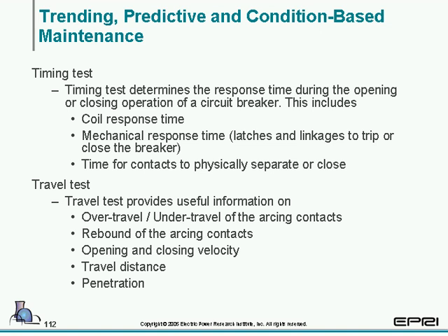The timing test is a fairly easy test to perform. The timing test can be done during a PM. A lot of times it is, but the travel test is a much more involved test. It requires much more setup, and it provides additional information for the extra work you have to do. It'll provide over travel and under travel of the arcing contacts, and this is in the form of an actual printout. It'll show you rebound when the arcing contacts rebound. The velocity by which when the breaker opens and closes, the moving contact assembly, there's a velocity associated with when it opens and when it closes, how fast it's going, the distance it travels, and the penetration. You can get all of this information from a travel test. Very worthwhile test, especially after you've done an overhaul. You want to make sure that circuit breaker operates properly.